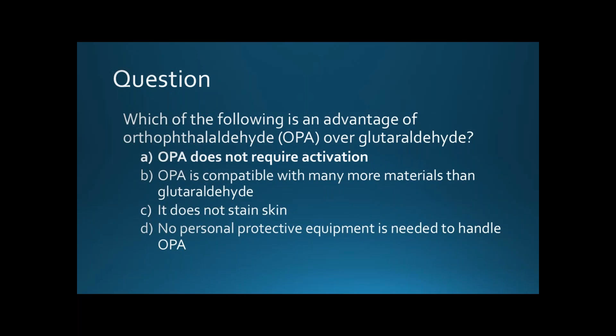So endoscopes are used all over the place, right? Especially for GI procedures. Contamination of a GI endoscope during use is 10 to the 9th organisms on the inside, in the lumen of that scope, and 10 to the 5th on the outside. So it's grossly contaminated. Yes, OPA does have to be deactivated before disposing, but not for use. You do need to neutralize it.